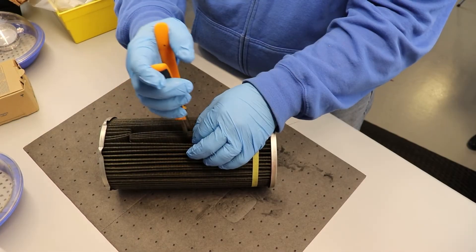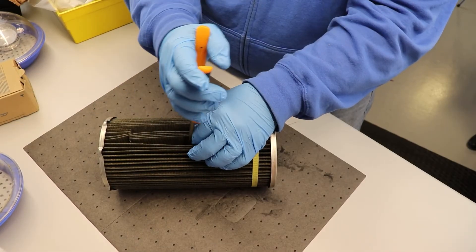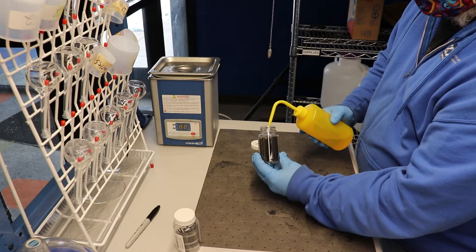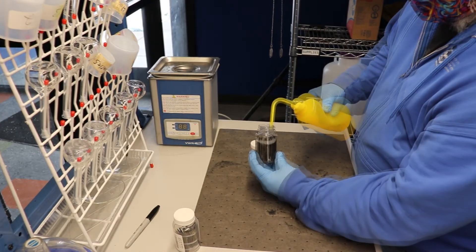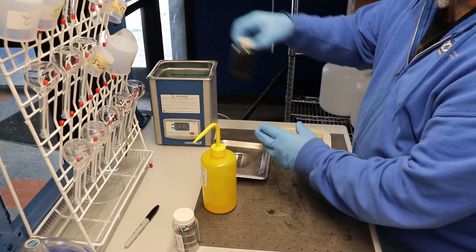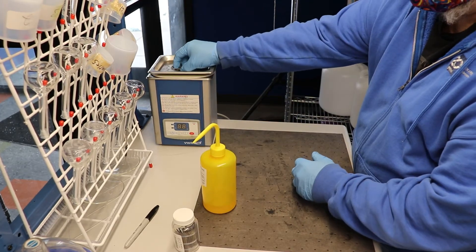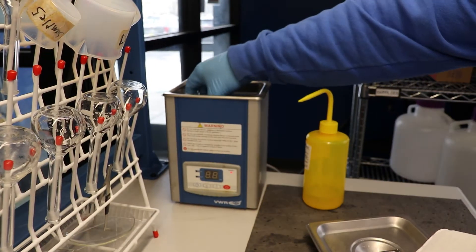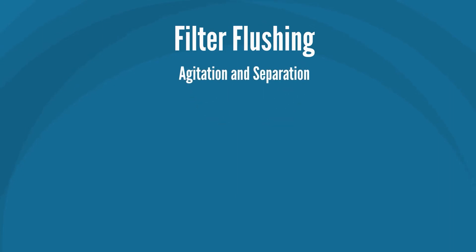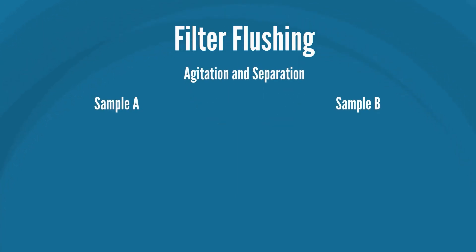Filter Debris Analysis is conducted by first cutting a pleat out of the oil filter. The pleat is then flushed with a solvent and is processed in an ultrasonic bath to remove any debris within the filter pleat. After processing in the ultrasonic bath, the filtered material is agitated and then separated into two samples, A and B.